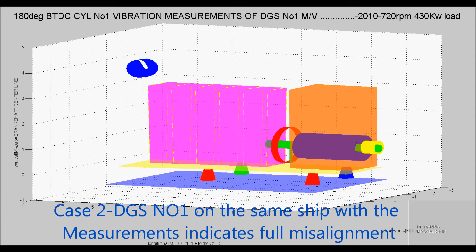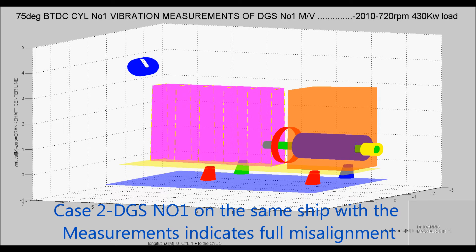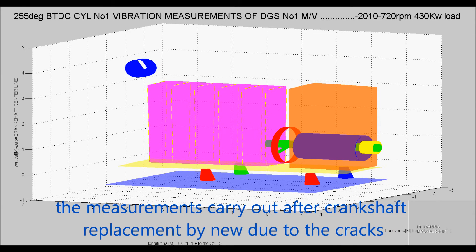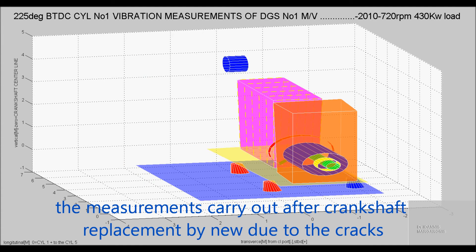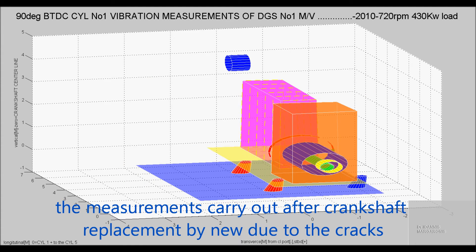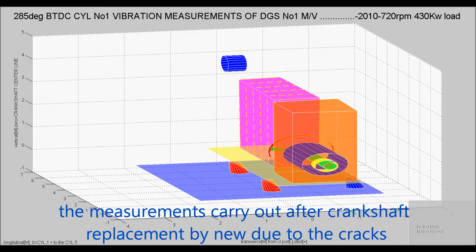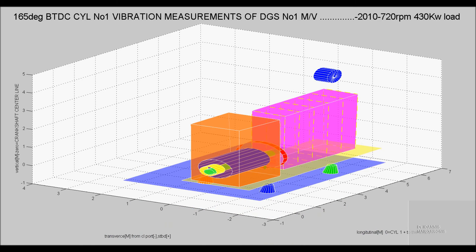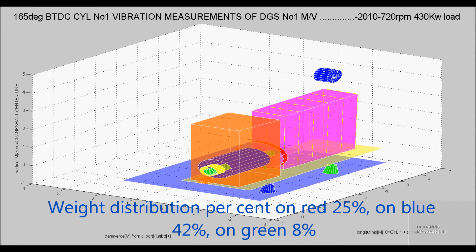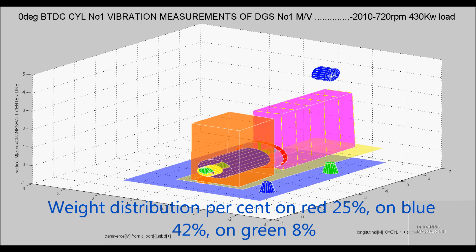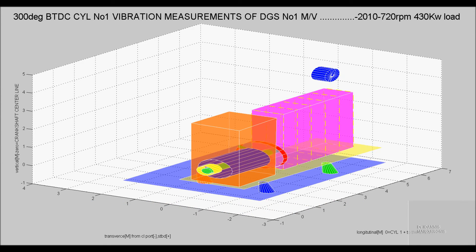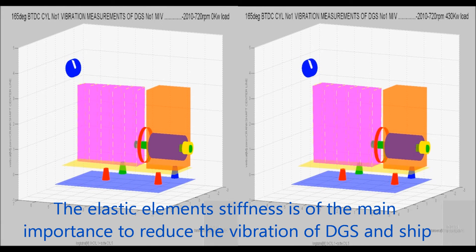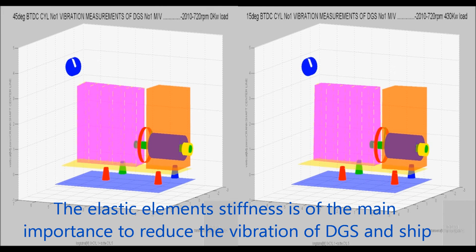Case 2: DGS number 1 on the same ship, where measurements indicate full misalignment. The measurements were carried out after crankshaft replacement with a new one due to cracks. Weight distribution shows: red mount 25%, blue mount 42%, green mount 8%.